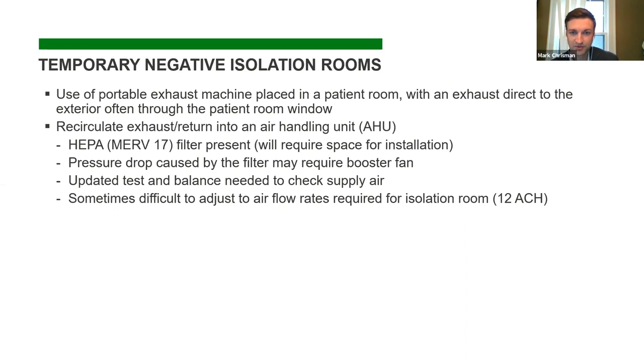And because we're adding this, in order to qualify for 12 air changes an hour, we need to update the test and balance in the room and actually check the supply to make sure we're not causing issues with pulling air out of the corridor or too much air from other places. Sometimes in older facilities we just don't have the makeup air or return air to be able to get the 12 air changes an hour.